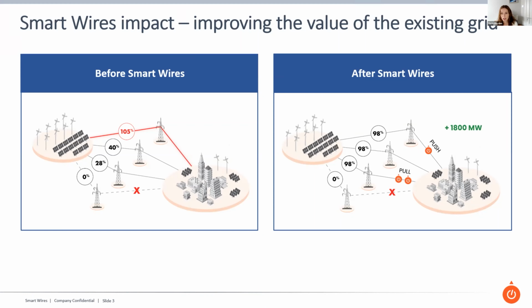So this combination of pushing power off overloaded lines and pulling power onto underutilized lines can unlock significant amounts of capacity on the grid without the need to construct new overhead lines. And again, another example of this, when we go and look at the Irish grid, is the application of series compensation to the 400 kV network between Moneypoint and Dublin, which is looking to do exactly this, to reduce the impedance of the 400 kV network, to encourage power to flow along that network, which is underutilized, and to divert it away from the overloaded 220 and underlying 110 kV network.